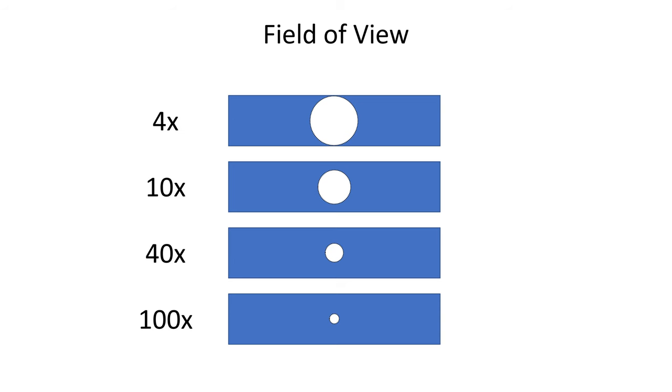I want to briefly cover two important aspects of brightfield microscopy before going to the oil objective and viewing chromosomes at 1000x. Number one, the field of view. This is the area of the slide visible through the eyepiece. When you increase magnification, the field of view decreases. That's why it's important that you use the stage controls to center any region of interest before switching to a higher power objective.